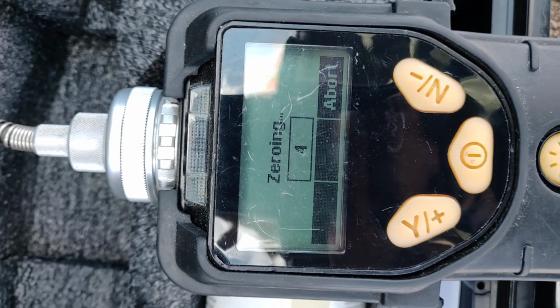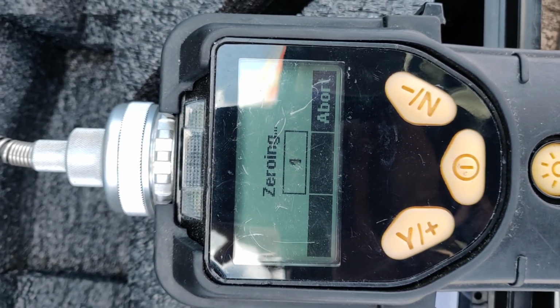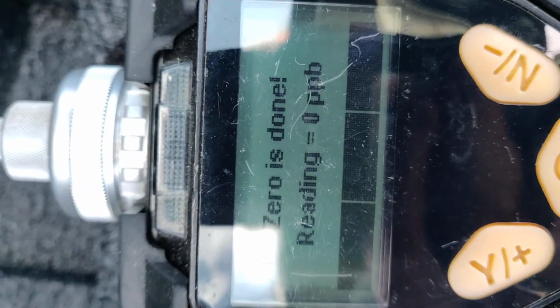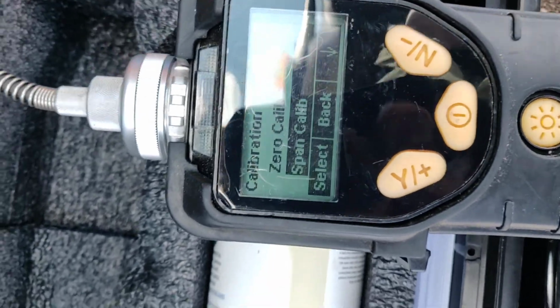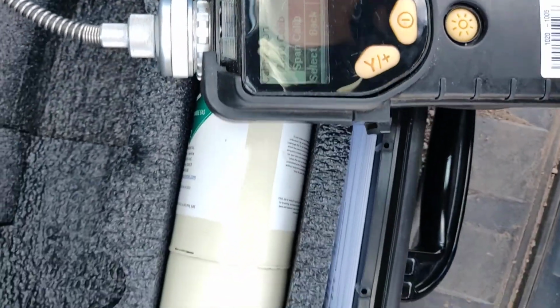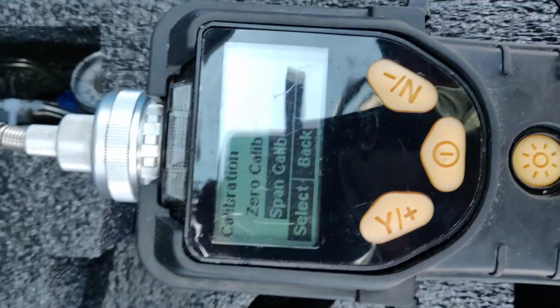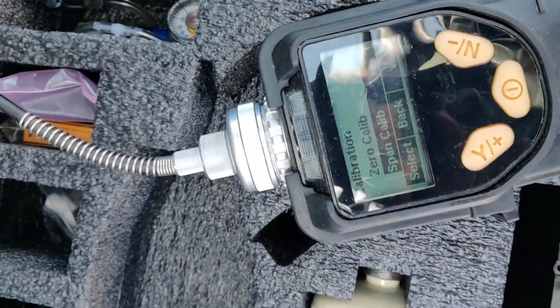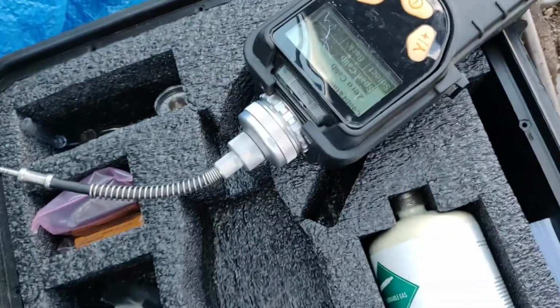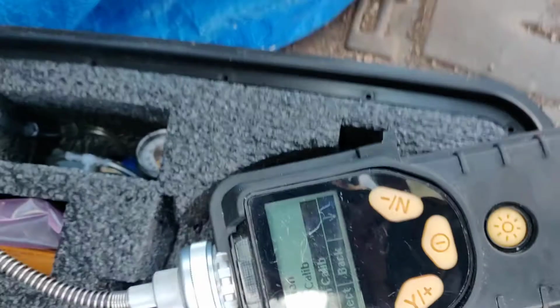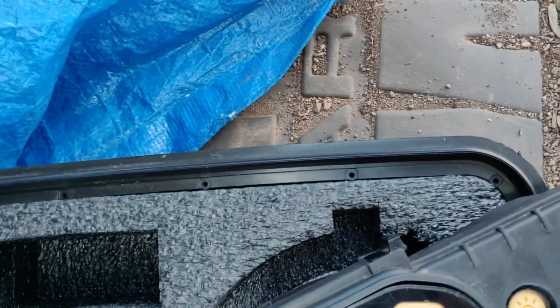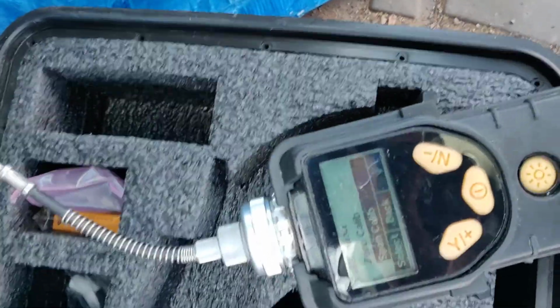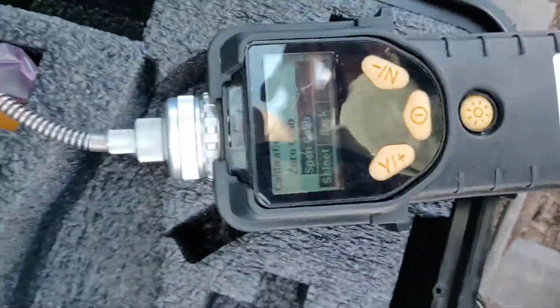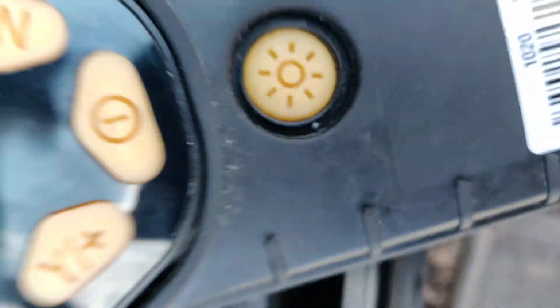The calibration goes towards the internal calculations. You see, you set a zero, and then we're going to set what's called a span. Using a zero and a span, you will have a range, and anything in between will be more accurate. It has a linear relationship going up, though we will not find anything in this environment, at least, above 10 parts per million. 10 parts per million is my span value. The reason we use 10 is that it's lower. Usually they go out with 100 parts per million if you're using the parts per million one. You following? I'm sorry, it's a little disjointed.